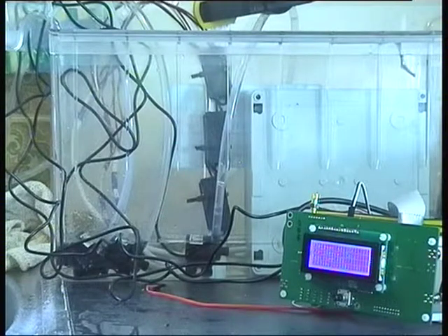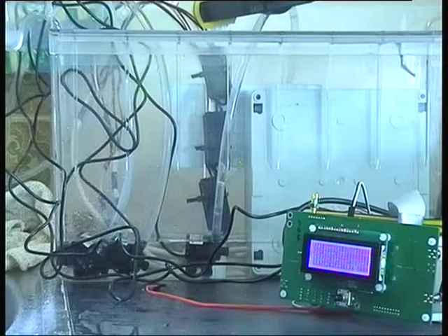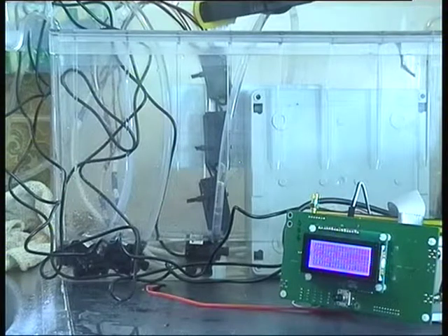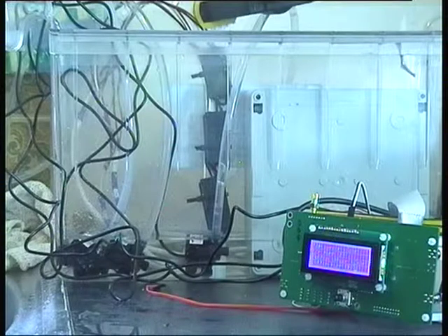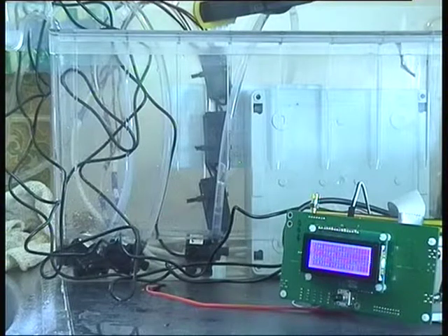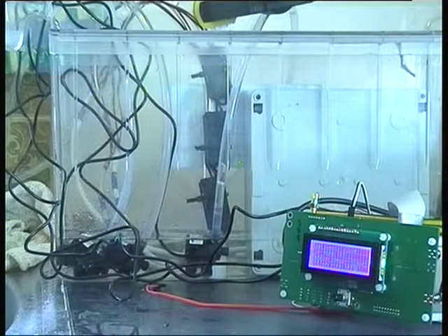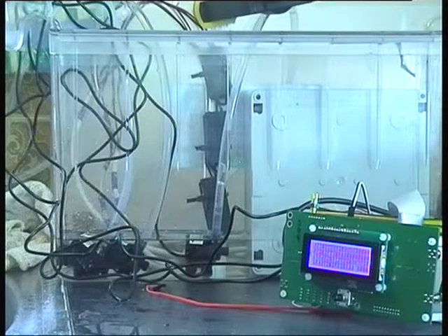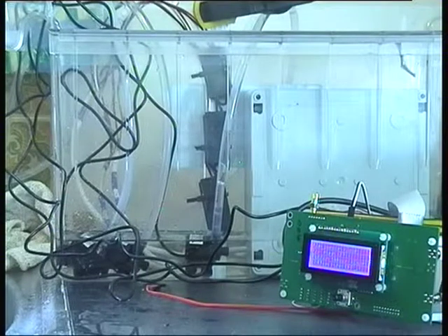One extra facility that we have with the microcontroller is when we get a fault condition, it sends an SMS text message to a mobile phone to alert an operator that we have a failure and somebody can be sent to look at the system. It also uses the Lora network to uplink to the LoraWAN network a message indicating failure, which can then be forwarded to a database to alert operators.